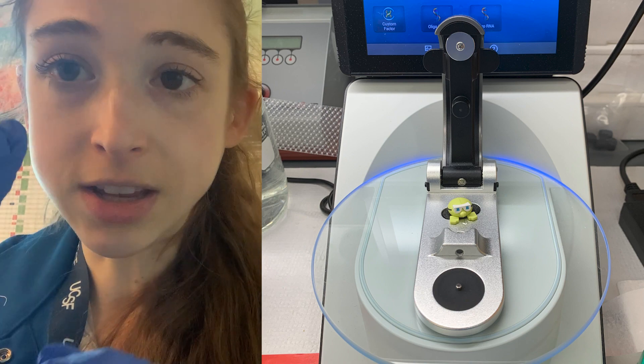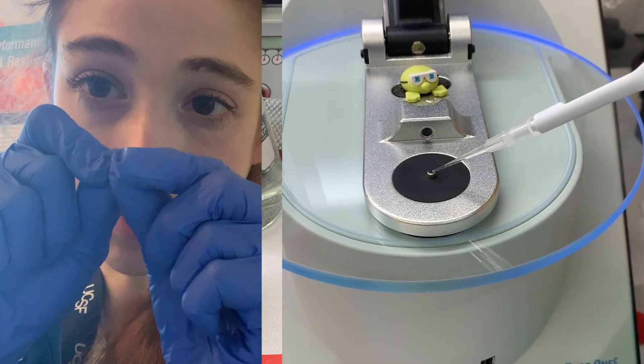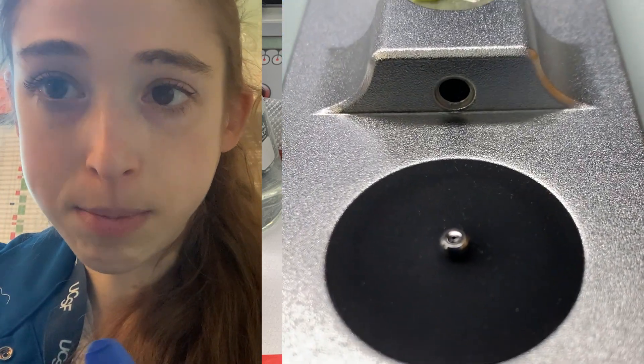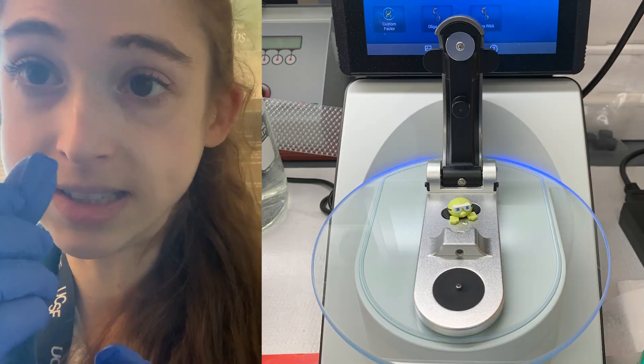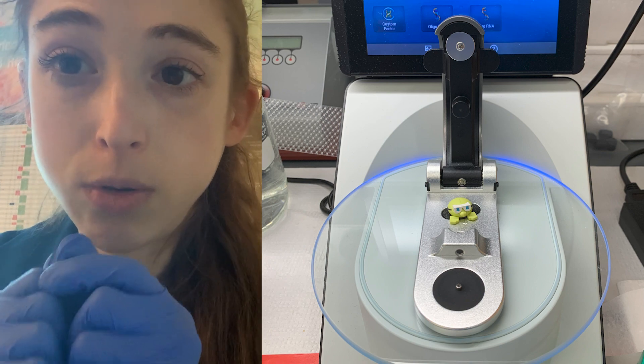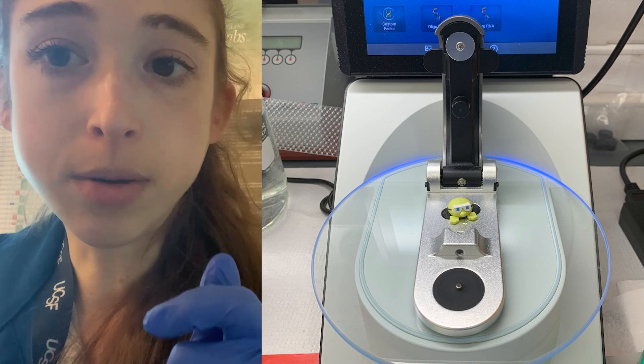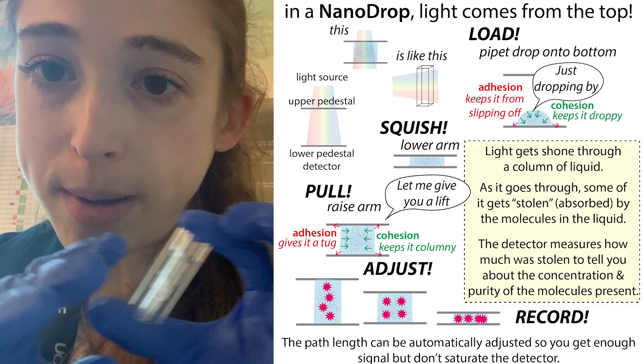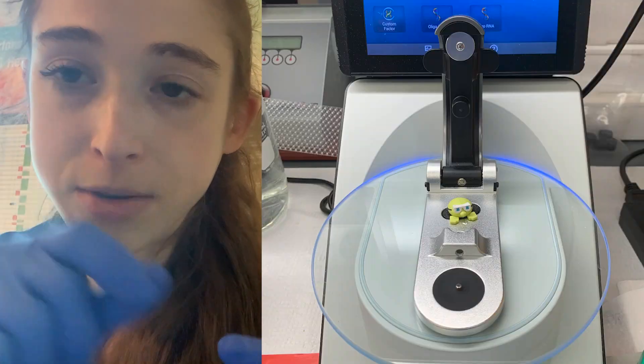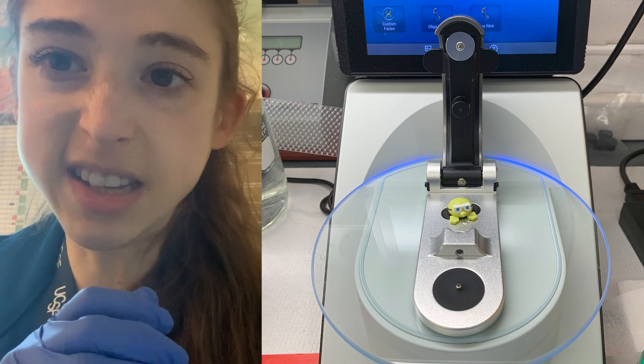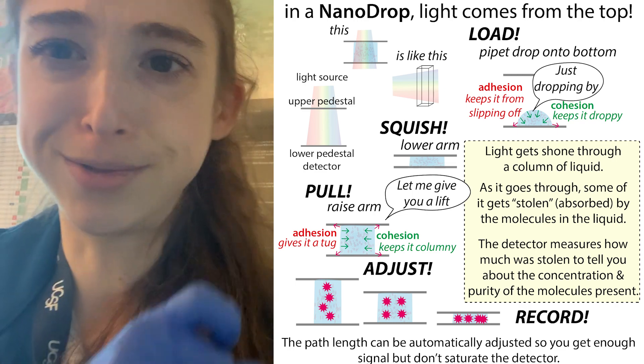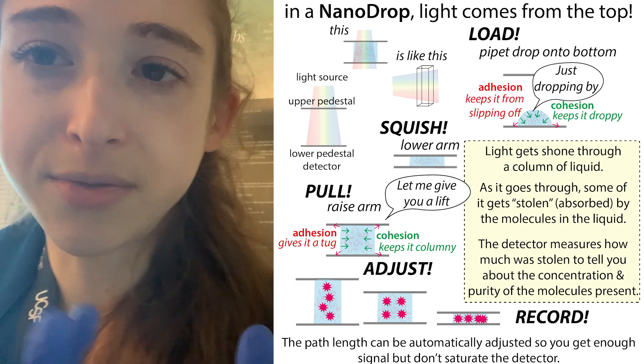Also be careful when placing the drop that it actually goes onto the pedestal over the hole where the light is passing through. I always check after pipetting that there are no bubbles and that the drop is right over the sensor - sometimes when pipetting you can accidentally push it off to the side. Also make sure to blank first: run a sample without your solution but with all the background buffer beforehand. And when you're done, wipe down the pedestal so you don't leave crusty residue for the next person, who might then think their sample is contaminated.